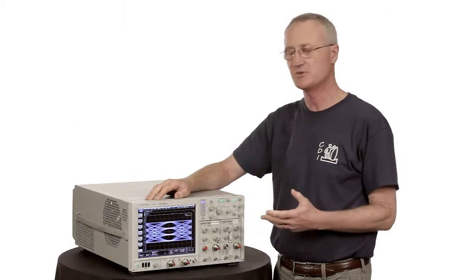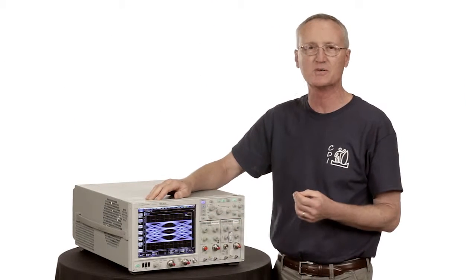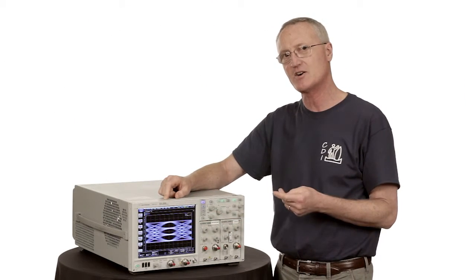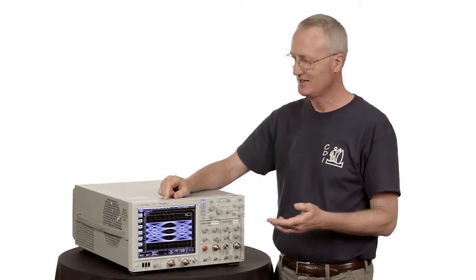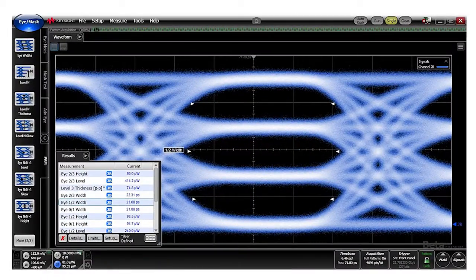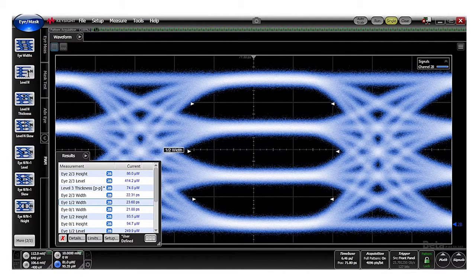Many of the PAM-4 measurements that are made on that eye diagram are similar to what was done on the NRZ eye. Things like eye width, eye height, except that if you notice here, instead of an eye width, there are three eye widths. There are three eye heights. So when you press the eye width measurement, it reports three values.